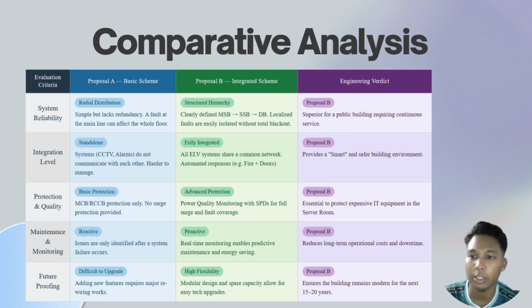And for the last part, 3.3, comparative analysis between proposal A and proposal B. There are a few evaluation criteria that we consider: system reliability, integration level, protection and power quality, maintenance and monitoring, and future proofing. So starting with system reliability, proposal A uses a simple radial distribution, but a single fault can affect the entire floor. Meanwhile, proposal B is a structured hierarchy with a clear layout from MSB to SSB to DB. So the fault can be isolated locally without a total blackout.